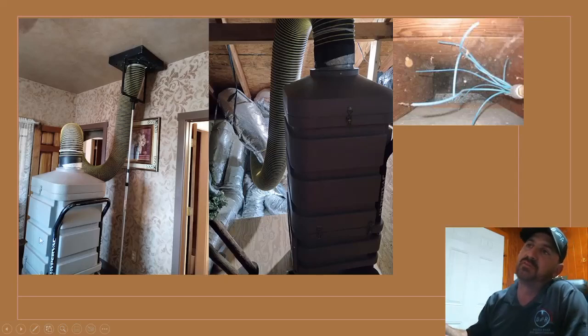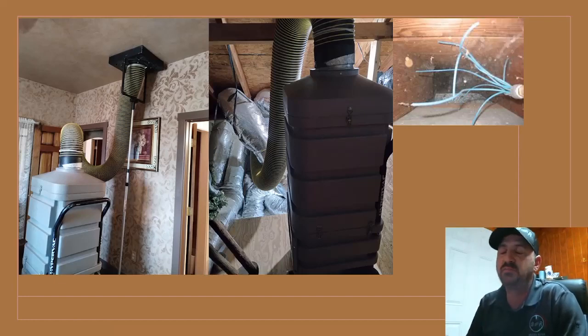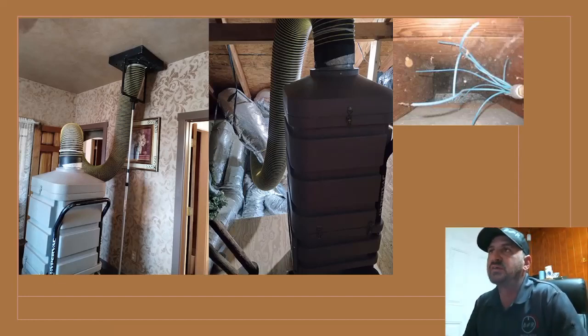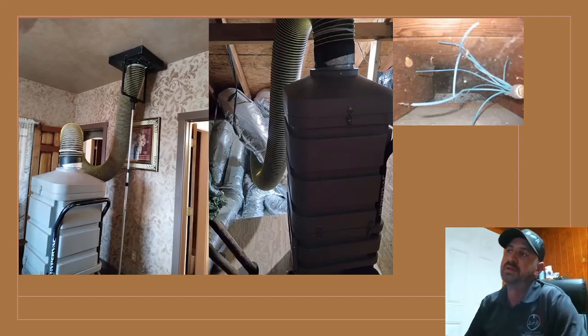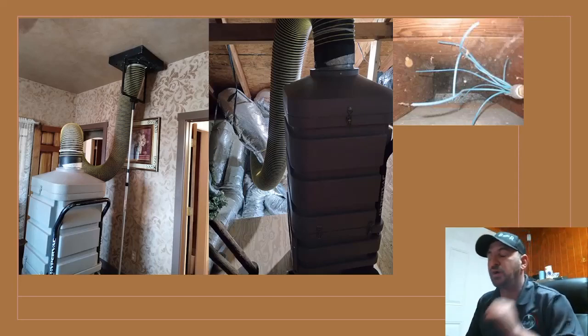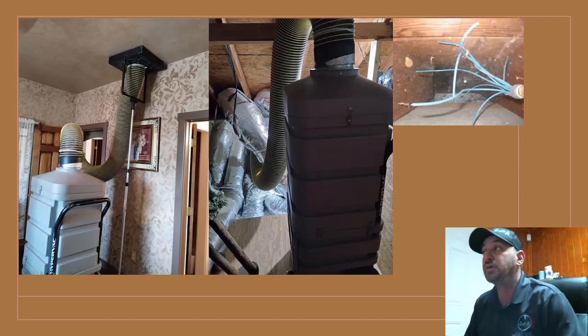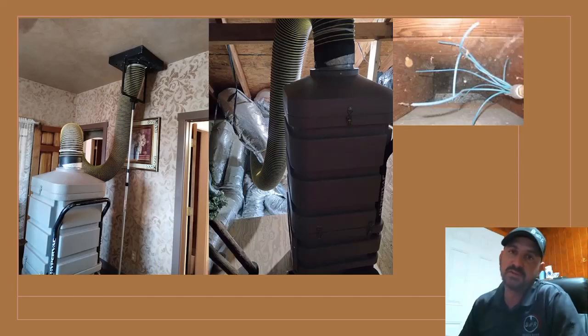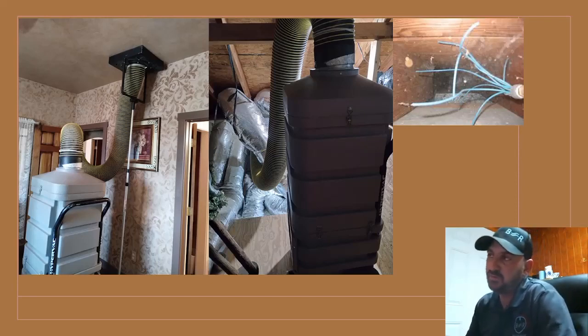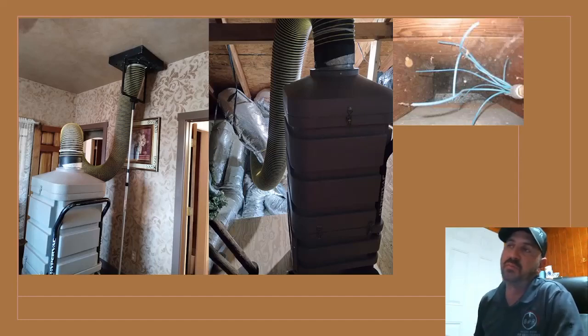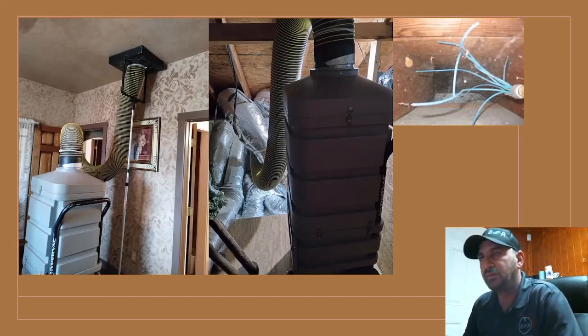Essentially you have this HyperVac machine. The machines he's using are variable speed, so they can change the CFM according to the system they're working on. Their CFM goes up to, I believe he said, 5,000, while your normal AC system has about 400 CFM per ton. So a 5-ton system, the largest residential system you can have, will be 2,000 CFM. So their machine will definitely pull more than your air conditioner can blow around, which is a good thing.